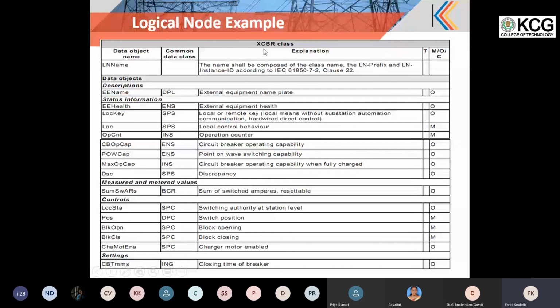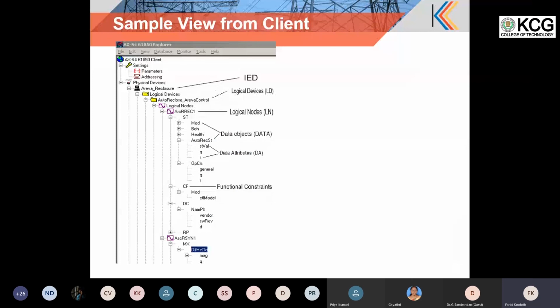Then blocking opening, blocking closing, those elements are also mandatory. Then operation command is another attribute. Count is another mandatory parameter. Like that, multiple optional parameters are there, and each vendor can define. There is a definition for all the optional parameters. Each vendor is flexible to include or not include them. So this is a sample view of a screenshot from a client side. With just giving an IP, I am able to explore all the logical nodes in the device, its data objects, data attributes, everything, including report and logging, from a client tool. Similarly, this can be achieved in a SCADA system also.